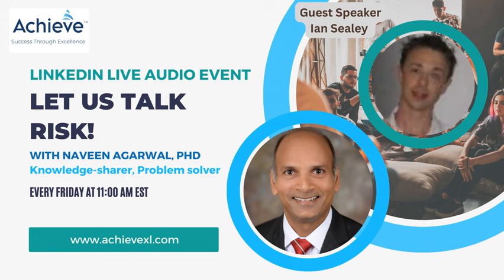And then I love how they also talk about technologically practicable or technically practicable. I can't remember the exact word, but they basically say, like, if you're putting so many warnings in the user manual that they're on warning overload or labeling overload, the thing's so covered like a billboard with warnings, nobody's going to read them all. Like, that's too far. If you're putting so many design controls in that you lose safety or efficacy because there's so many steps, it takes so long, it takes such intense training or checking of the training that you don't get the benefit of the risk control.